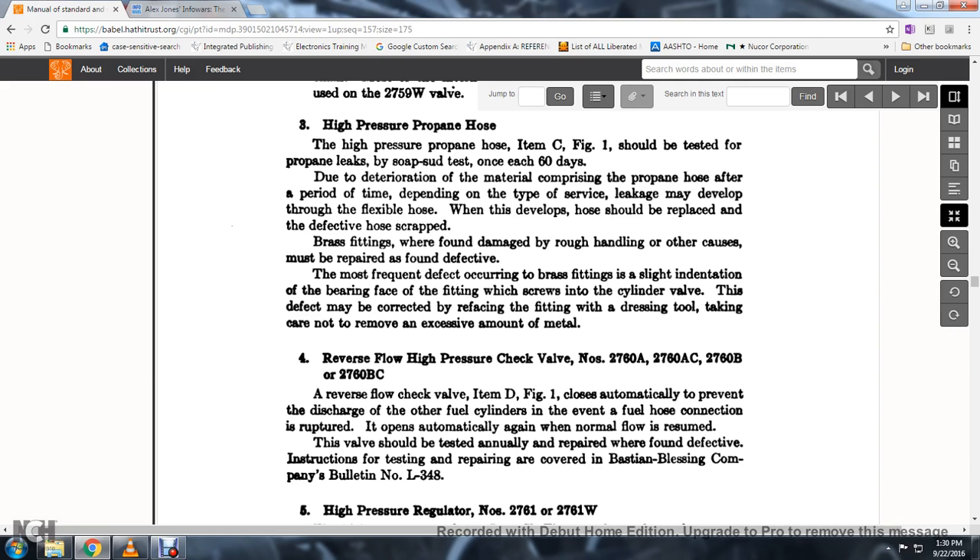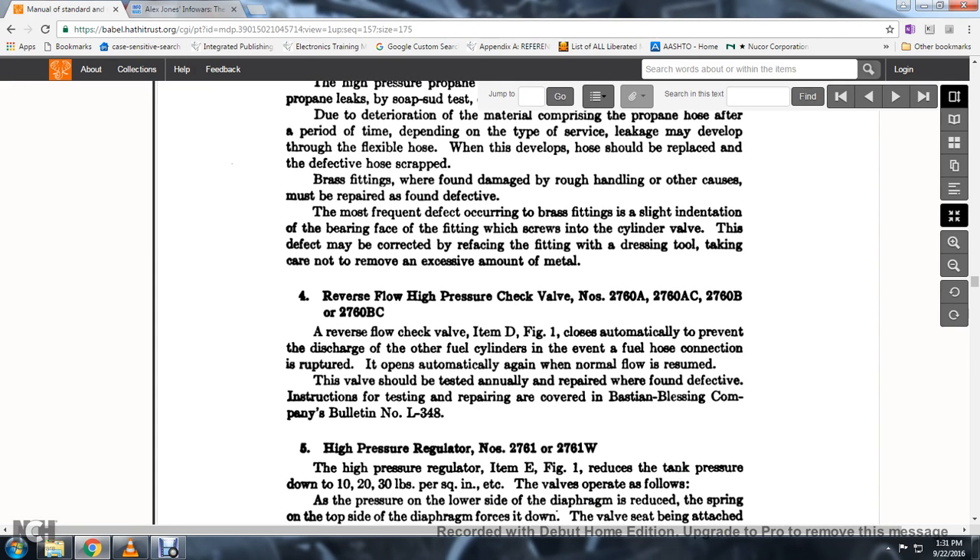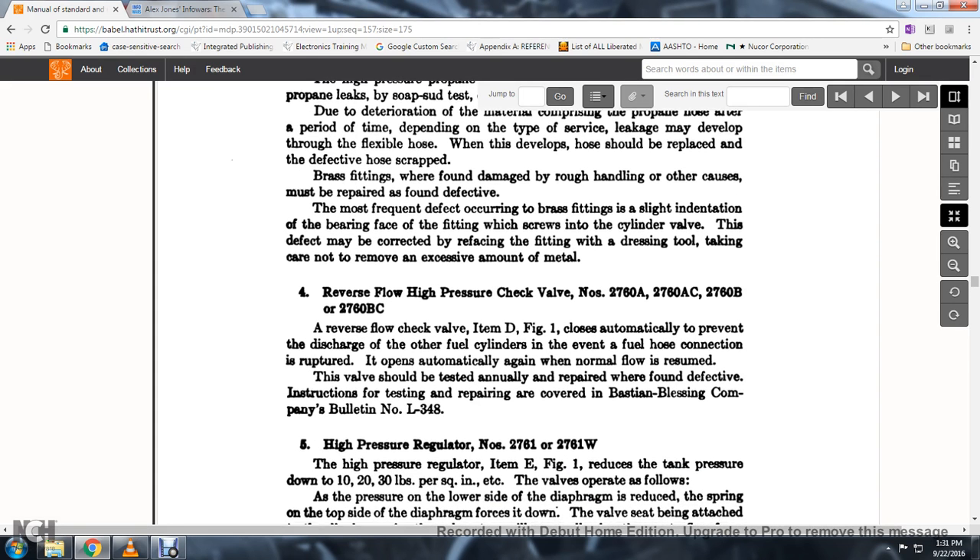Reverse flow high-pressure check valve No. 2760-A, 2760-AC, 2760-B, 2760-BC: the reverse flow check valve, item D, figure 1, operates automatically to prevent the discharge of flow from fuel cylinders in the event of a broken fuel hose connection. It opens automatically again when normal flow is resumed. The valve should be tested annually and repaired when found defective; instructions for testing and repair are covered in the Bastian-Blessing Company Bulletin No. L-348.